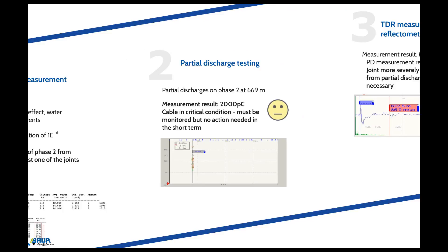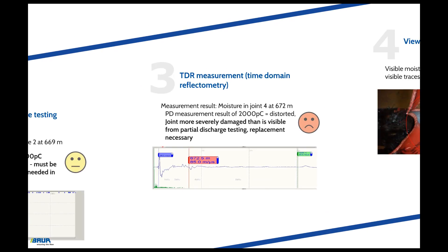In our example, the dissipation factor measurement shows a deviation of phase 2 from the normal value, which leads to the conclusion that there is moisture in at least one of the joints. The subsequently performed partial discharge testing identifies partial discharges on phase 2 after a length of 669 m. The partial discharge level of 2000 pC leads to the conclusion that the cable is in a critical condition, but the results of the partial discharge testing do not necessitate immediate action. Only by overall consideration of the results together with the dissipation factor measurement can the condition of the cable be determined. The TDR measurement, which is also used for the location of damp joints, shows that the moisture in joint 4 lies at 672 m. The fault location identified in the example coincides with that from partial discharge testing.